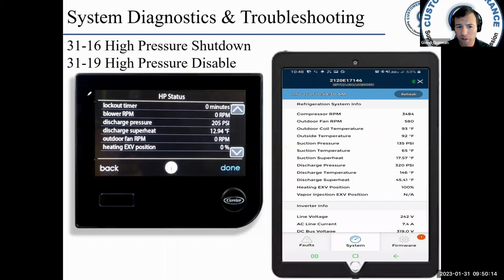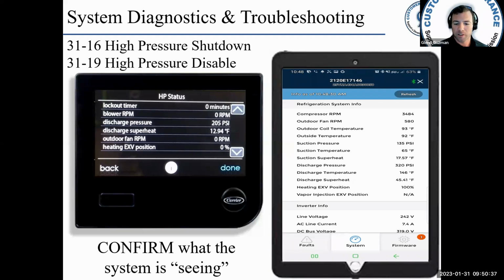Okay, continuing on, 3119 high pressure disable. Look at the UI, look at the app, and find out what my pressures are, and connect your gauge. What are my pressures on my gauge reading? Okay, do we actually have a high pressure condition? That's not allowing the compressor to start. So confirm what the system is seeing. Right? Discharge temperature, discharge pressure.